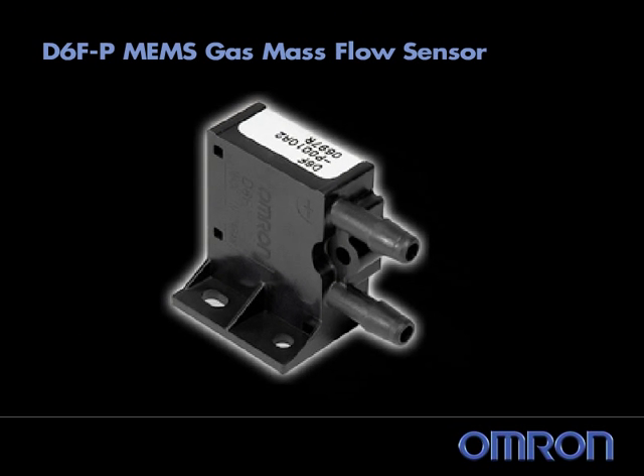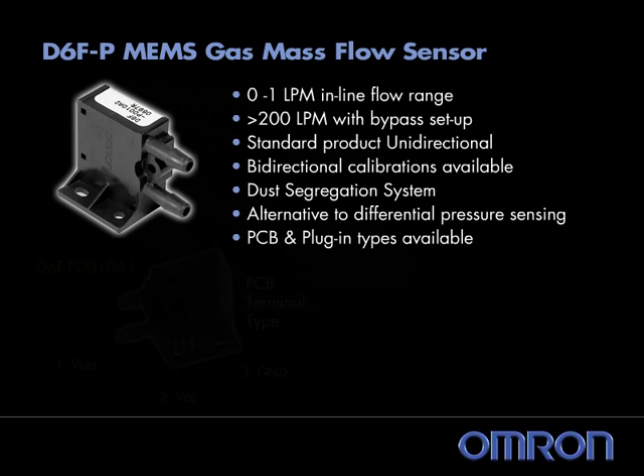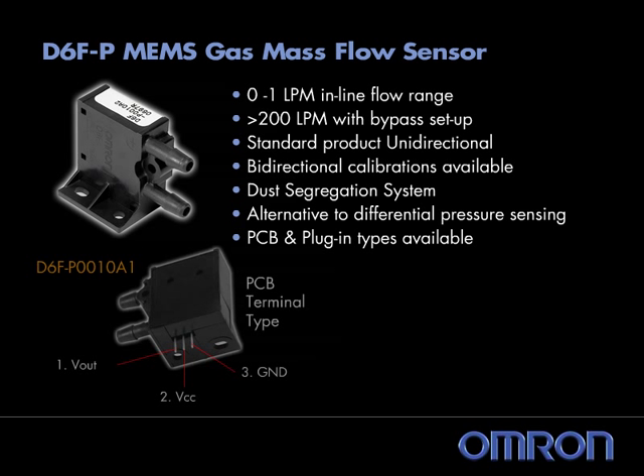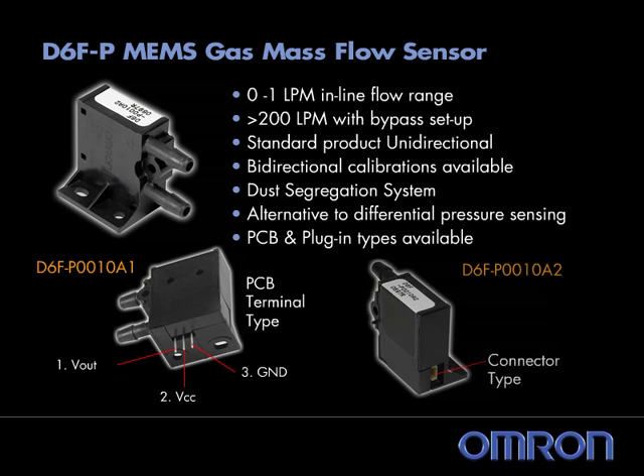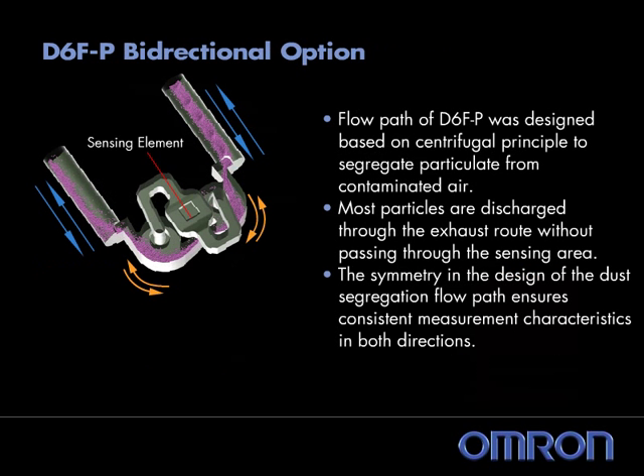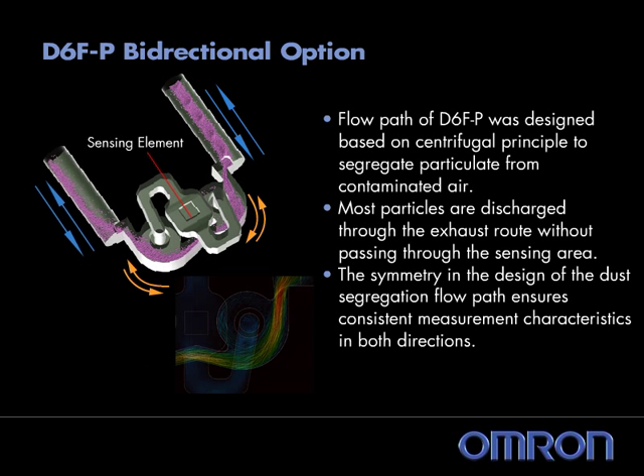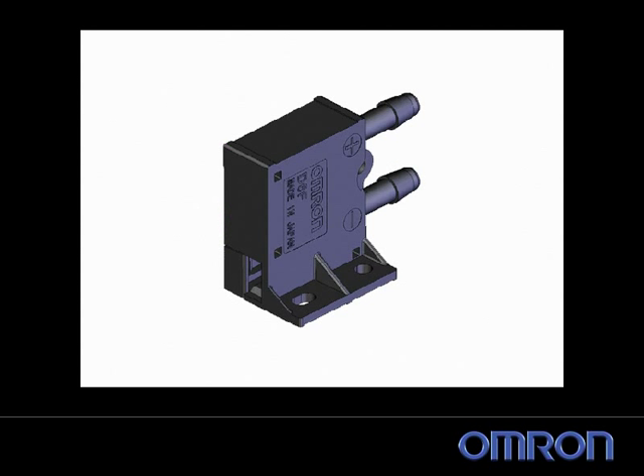The D6FP model is available in two packages: a PCB terminal and plug-in type. It can measure up to one LPM in-line or be used in a bypass setup for much larger flow rates as an alternate to differential pressure sensing. Having both flow ports on the same side simplifies the customer's design and installation. The symmetry of the design makes it possible to accurately measure flow from either direction.